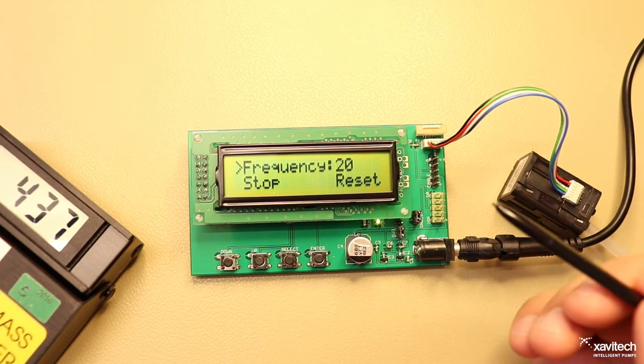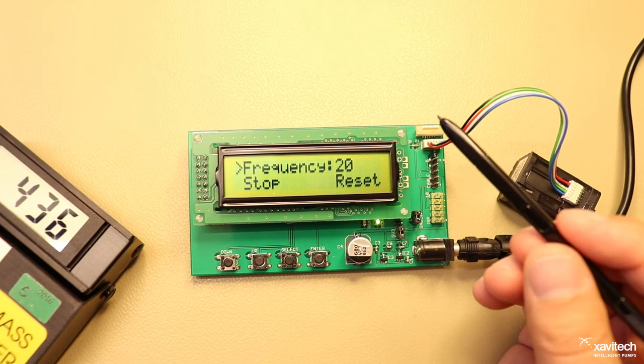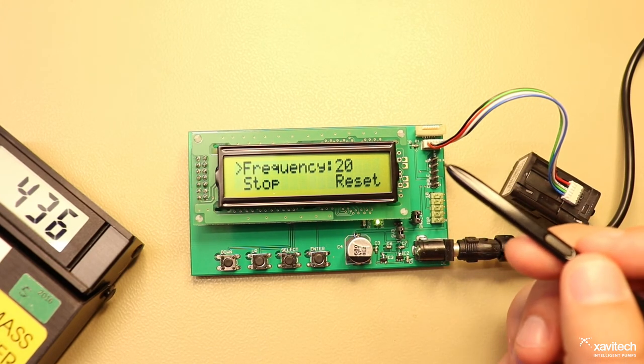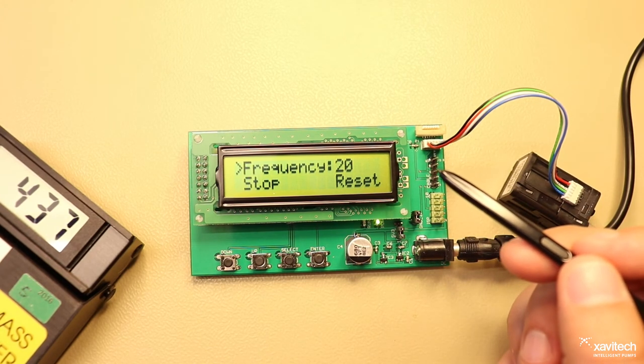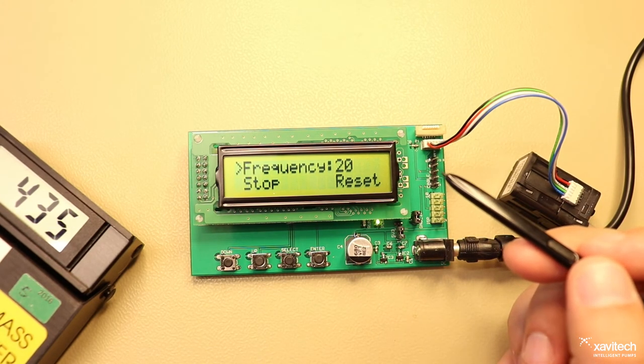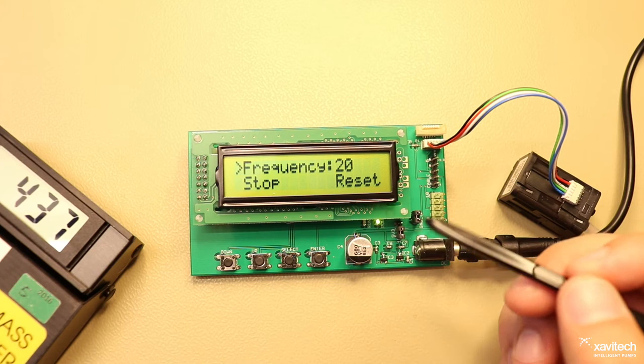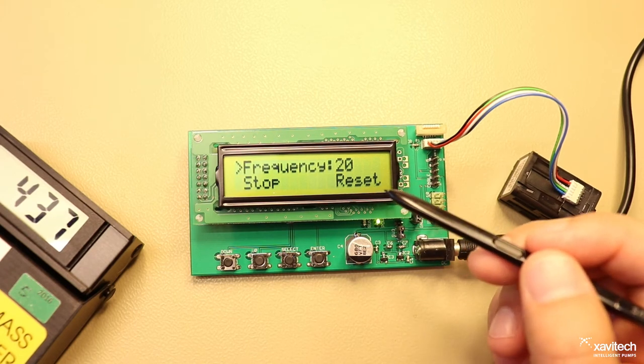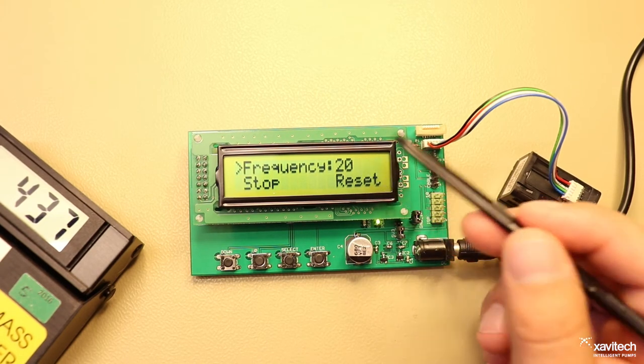During production each pump is calibrated to a certain frequency value together with other parameters. When you first start the pump with the FCU you will see this frequency value.